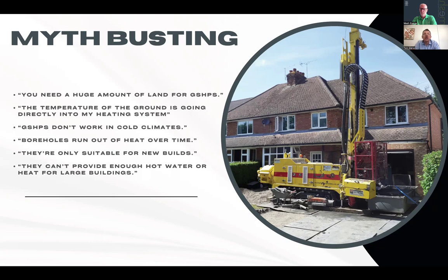I still wouldn't agree with this. I can understand what Julian's saying. The efficiency of the air source heat pump is better than it used to be because of the refrigerant and stuff like that. But there is still a gap between the efficiency of the ground source heat pump and air source heat pump. So it will probably be better than running this on oil or something like that. Efficiency is still better, but you are still not going to beat a ground source heat pump with an air source heat pump.